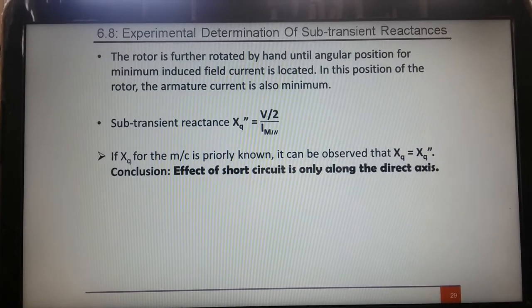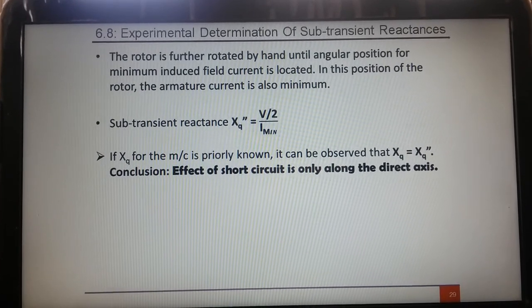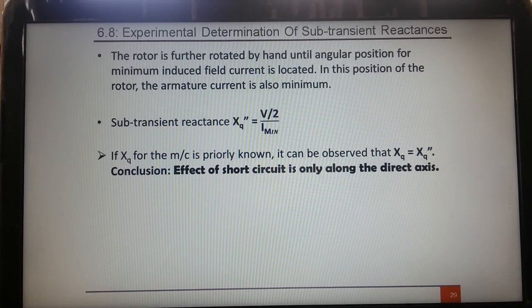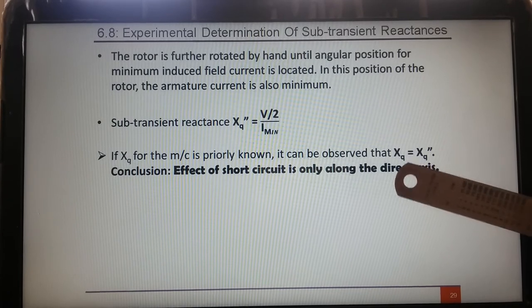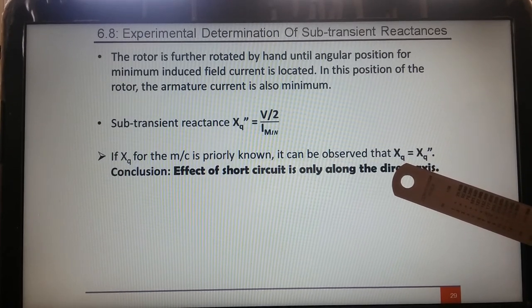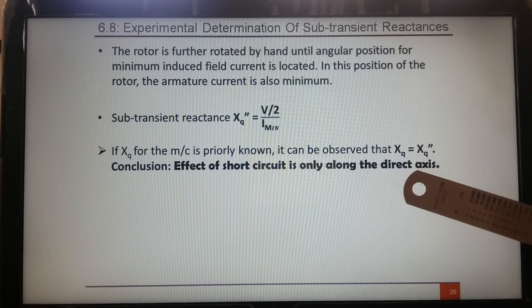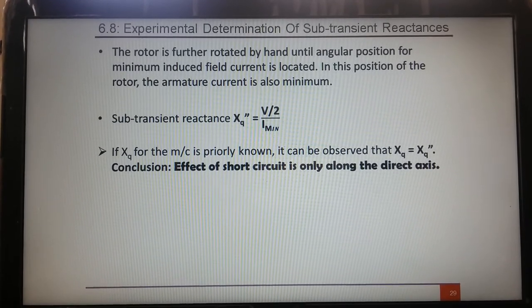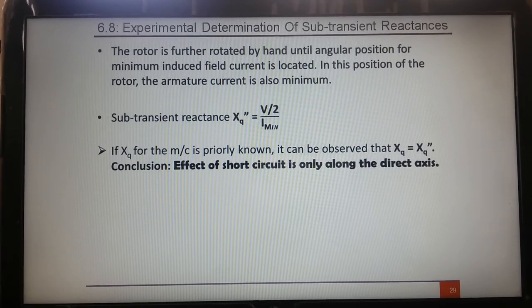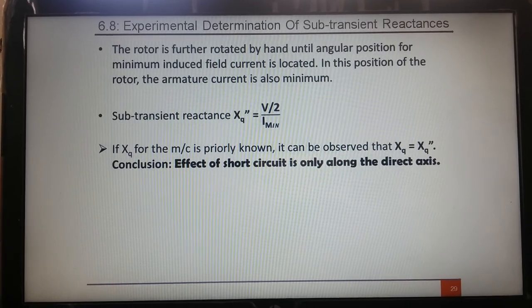As discussed in the last videos, the effect of a sudden short circuit or sub-transient phenomena exists only along the D-axis. That is why XQ equals XQ double dash. If you find XQ double dash, it is equal to XQ which you already get from the slip test, so there is no need to recalculate XQ double dash. The effect of short circuit is only along the direct axis. In this way, XD double dash and XQ double dash — the sub-transient reactances along the D-axis and Q-axis — have been experimentally determined.